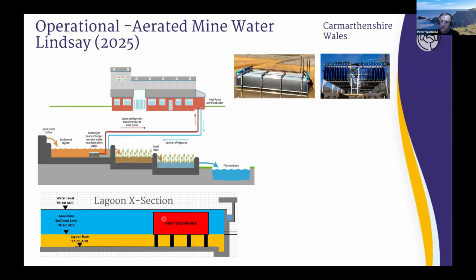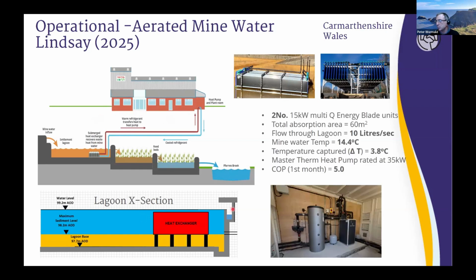You'll see at the bottom section that we've learned from our field trials, and to avoid any drop-off in performance, as the energy blades were lowered into the lagoons, they were mounted on legs to prevent ochre buildup on the plates. Here we've installed two 15 kilowatt multi Q Energy Blade units into the lagoon, accessing mine water flow of 10 litres a second, 14.5-degree mine water, and a delta T of approximately 4 degrees. That gives a very healthy COP for the first month of operation for the scheme.